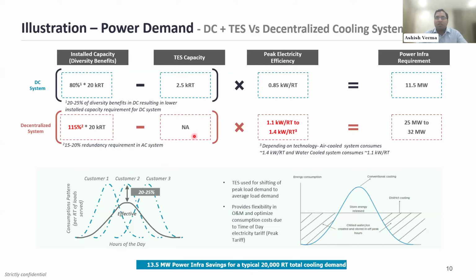Normally the efficiency varies from 1.1 to 1.4. 1.1 is for a water-cooled system and 1.4 is for an air-cooled plant. This translates to a power infrastructure requirement of 25 megawatt to 32 megawatt, and that's a huge difference, as you can see. So 13.5 megawatt of power savings can be achieved if we go with a district cooling plant coupled with a thermal energy storage system as compared to conventional plants.